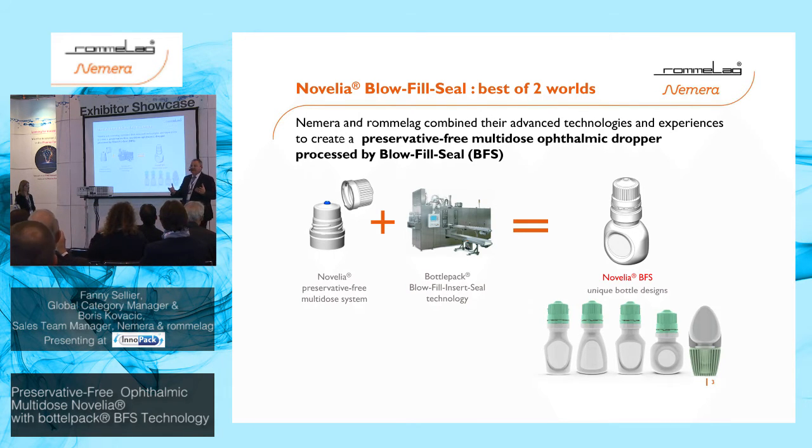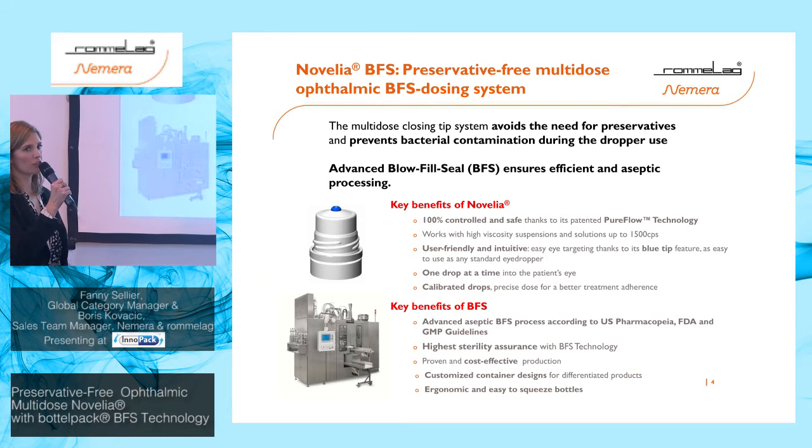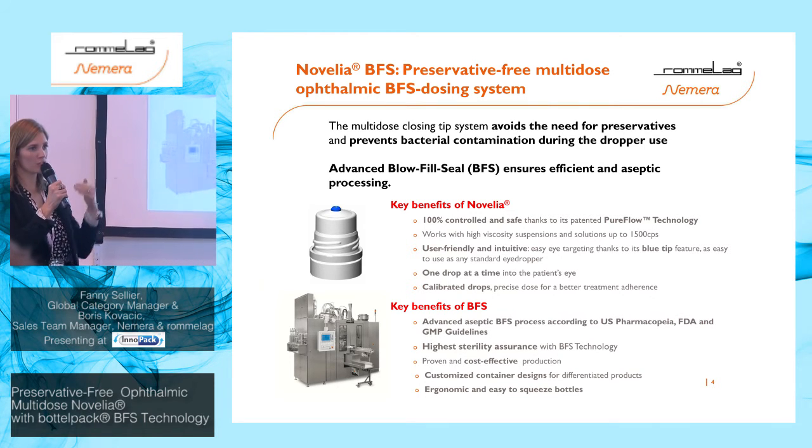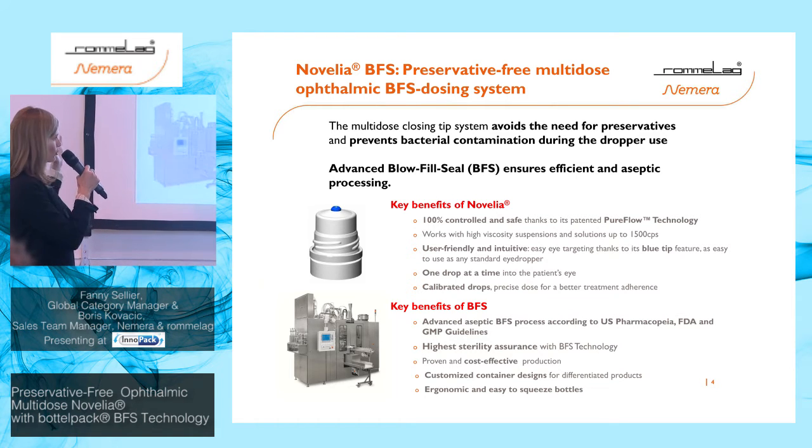This technology delivers a multi-dose preservative-free solution, meaning you don't need to add preservatives to the formulation — the system itself protects the formulation against potential contamination throughout the full treatment. The benefits of the Novelia system include 100% controlled and safe dispensing: all devices are controlled on our assembly line. It also features PureFlow technology, and works with suspensions, emulsions, and solutions ranging from very liquid to very viscous formulations — tested up to 1,500 centipoise.